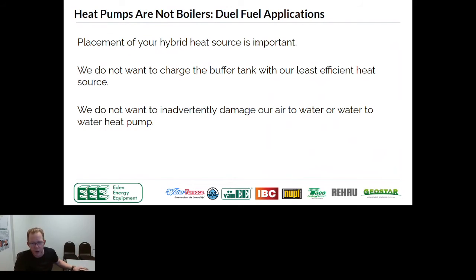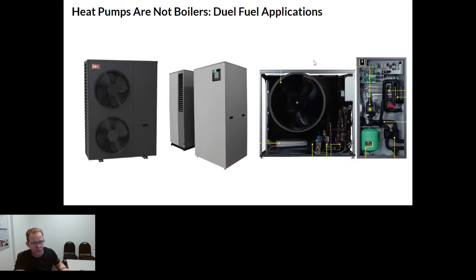The biggest thing we want to make sure we don't do is that if we have an air to water or a water to water, which we already said, if we put it into 140, the red light goes off and we've got a problem. We want to make sure we never pipe our backup source, whether it's a gas boiler or an electric boiler, so that it can inadvertently feed water back to the unit that's hotter than it should be. Now, you might think that could never happen. I would tell you one of the most common tech site visits I have to do is to address this issue right here. So if you take anything away from this slide, pay attention to where your backup boiler is in relation to the heat pump. There's absolutely nothing wrong with taking this dual fuel approach.